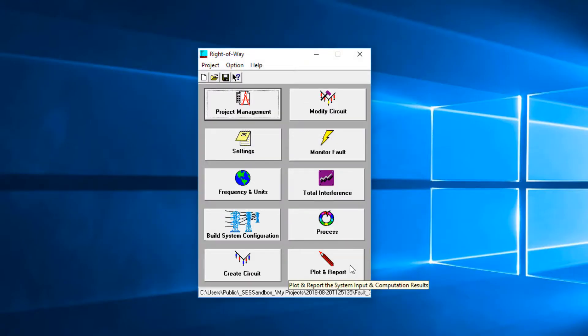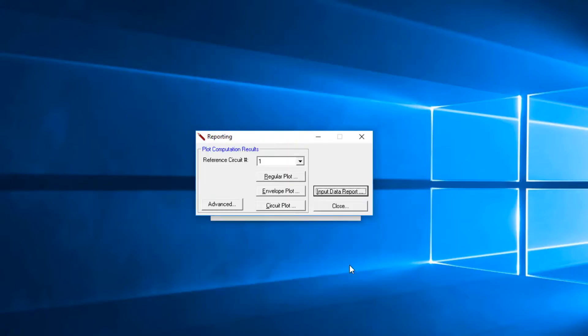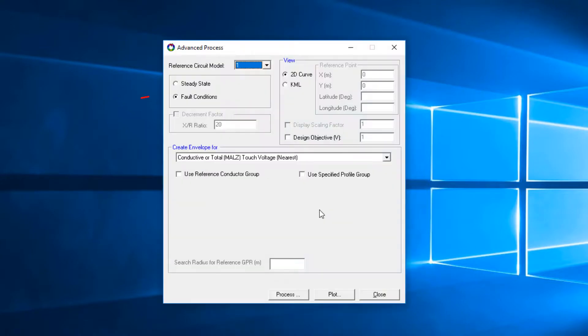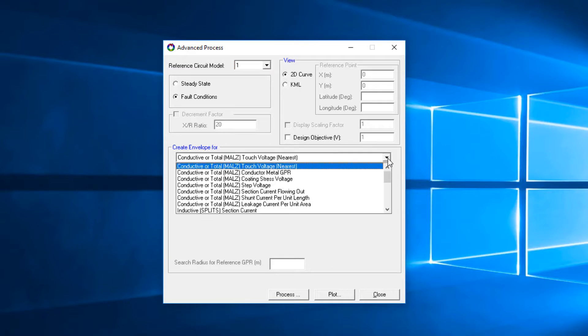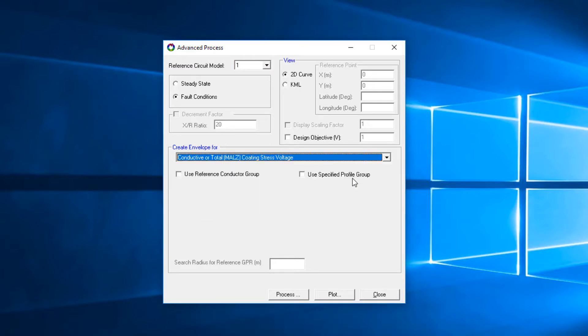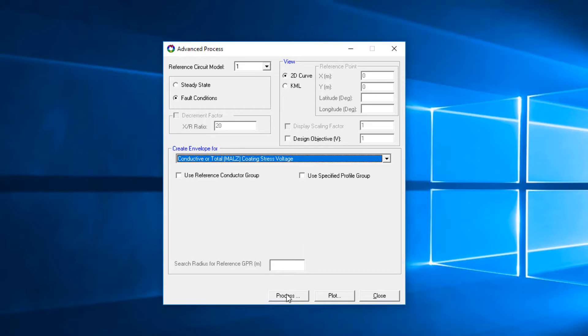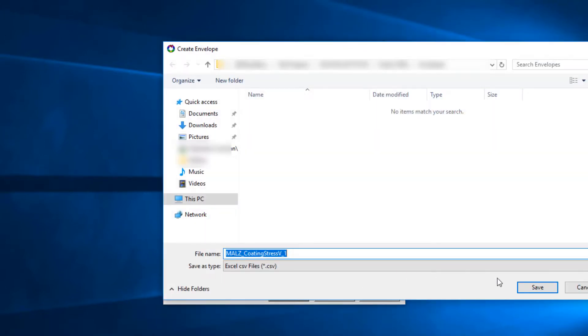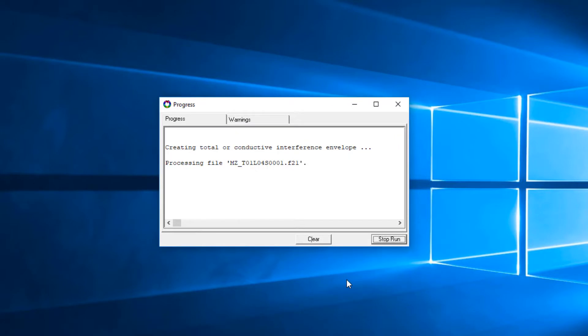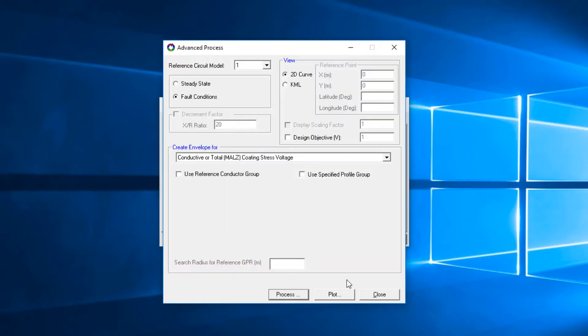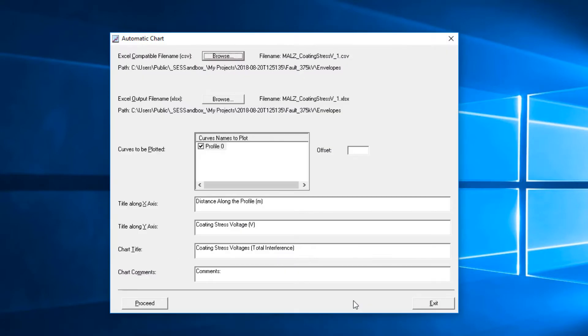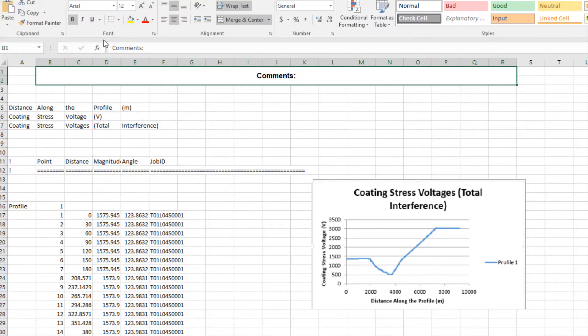Click Plot and Report to go to the Reporting screen. Then click Advanced. Select the Fault Conditions option and select Conductive or Total MALZ Coating Stress Voltage. Click Process. Save the file. The program will then parse all the results file and build the envelope of maximum values encountered. Then click Plot. The following screen will appear. Click the Process button. The Coating Stress Voltage envelope for default conditions is obtained.